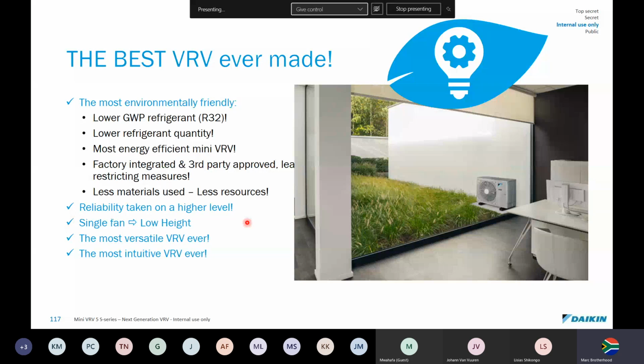Most energy efficient mini VRV. It's got factory integrated, third-party approved alarms and leak detection systems. There's less material used in manufacturing. So Daikin say that less resources are required, it runs cheaper and has less environmental impact. Reliability is taken on a very high level. It offers a single fan, which results in a low height. Very versatile unit, and it's the most intuitive VRV ever designed because of the leak detection and shut-off valves technology.